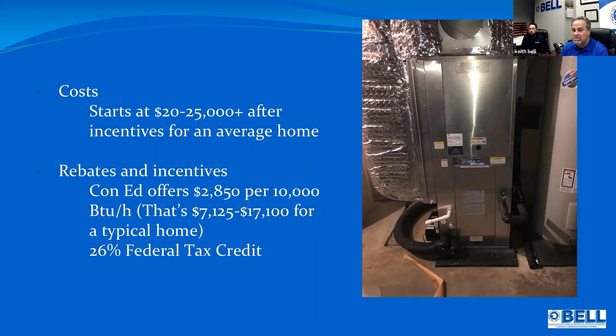So we are offering a free duct leak test whenever we clean your ducts. We can actually show you how bad your ducts are leaking. We have a thing called an AeroSeal machine. Like we talked about, you want to make sure your drafts are controlled. If you have existing ductwork, I can almost guarantee you that they're leaking. It's unbelievable. Back in the old days, we figured 5, 10, 15% leakage was acceptable. Not when you're paying this much for energy. And the new code requires a much lower leakage rate.